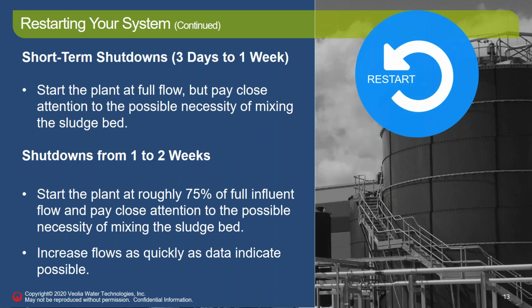So for short-term shutdowns, 3 days to a week, once you get things started again, just start up where you left off. Start at the flows that you were operating at when you shut down. If you're down for more than a week, a couple of weeks, you want to start up a little more slowly. So if you were taking 100 gallons per minute influent flow to begin with, you want to maybe try starting at 75% of that, 75 gallons per minute. Again, you've got to pay close attention to getting the sludge moving again. And once you get the gas production up, that mixing will all be taken care of by the gas production. Check your VFAs, maybe once a shift, so that you can increase your influent flows as quickly as possible. And the VFAs are going to tell you whether you can do that.